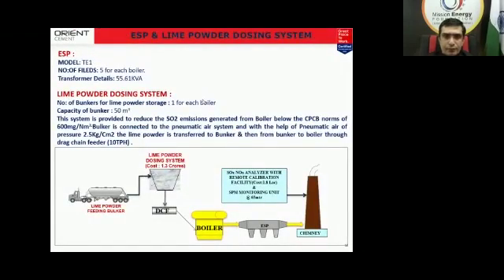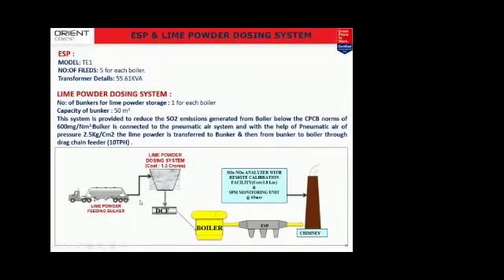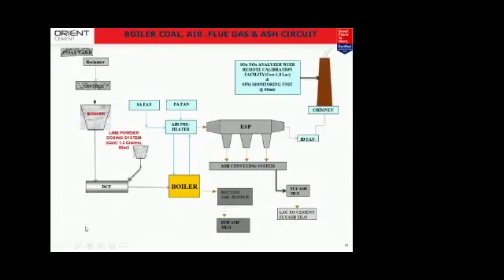Yeah. So as you can see, I described that we fill the lime powder ready-made from our cement plant into the limestone bulkers, and we take this bulker down to our power plant, and through a pneumatic conveying system we pump this lime powder into the lime dosing system bunker. From the lime dosing bunker, it directly goes into the DCF chamber, that is the drag chain feeder chamber, where it mixes with the coal. As you can see, there is a coal bunker, and it also comes into the DCF chamber. It mixes with the coal, and along with the coal, it is pumped into the boiler.